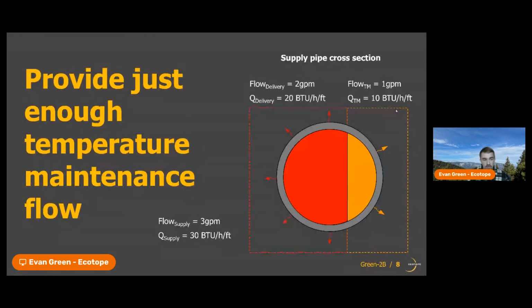And it actually is important to be able to talk about these flows differently, because again, I'll talk about heat pump water heaters because it's been at least 2 minutes. Heat pump water heater systems can actually heat this delivery flow a lot more efficiently. They really like heating cold water up to a high temperature. But this temperature maintenance flow returns at maybe 110 degrees Fahrenheit, and heat pumps find a lot more difficulty in heating that warm water back up to a high storage temperature. So this temperature maintenance flow is actually reheated a little bit less efficiently in most of these really high efficiency water heating systems.